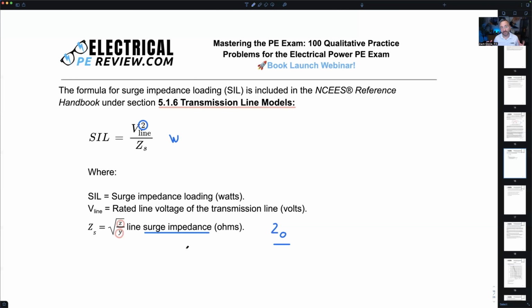All right, any questions? This is a really in-depth qualitative question. I can think just off the top of my head, easily 10 to 15 qualitative questions that you could expect to see on the PE exam based on the information we just talked about right now. Any questions? I would categorize this one as a harder one too. Typically, characteristic impedance is what you see come up more often, but being aware that it's also the surge impedance and that we can use the surge impedance to calculate the surge impedance loading, and then knowing what effect the load on the transmission line has when we compare it in size to, is it bigger than our surge impedance loading? Is it equal to our surge impedance loading, or is it smaller than our surge impedance loading?